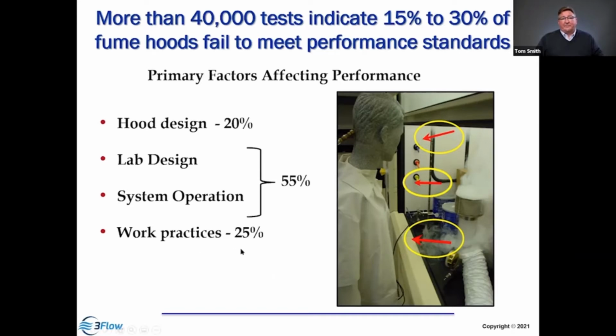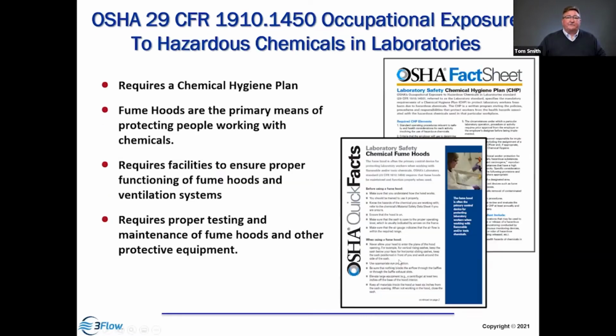And then 25% of the time it's due to work practices. So how is the hood being used? Do the occupants understand the capabilities and limitations of the hood? Dr. Gerhard Knudsen was the inventor of the ASHRAE 110 method of testing. And he has told me, he said, Tom, we can idiot-proof these systems, but we may not be able to PhD-proof them, right? We have very interesting people doing interesting types of research, and we may not be able to predict exactly how they need to use the hood. And that's why it's very important that we understand their needs and then we test the hood accordingly. So we want to make sure that we've identified these risk factors and look at how we fix them.